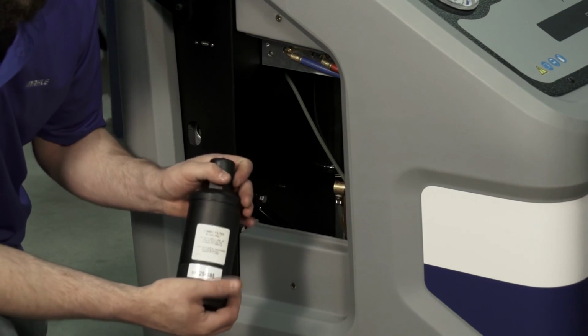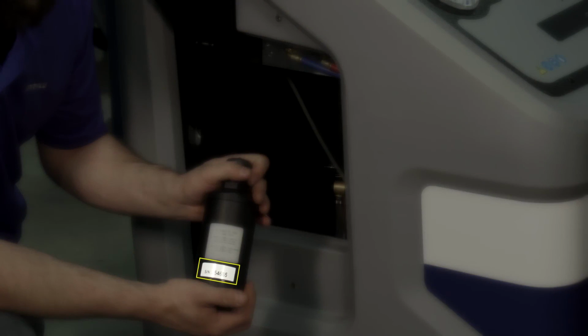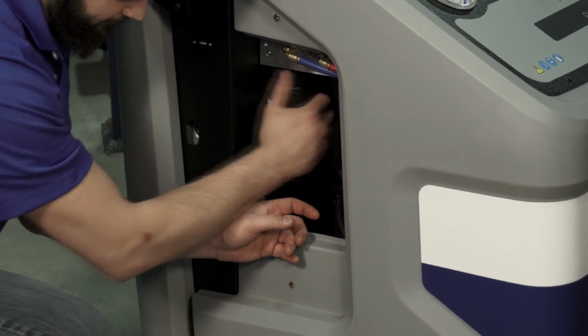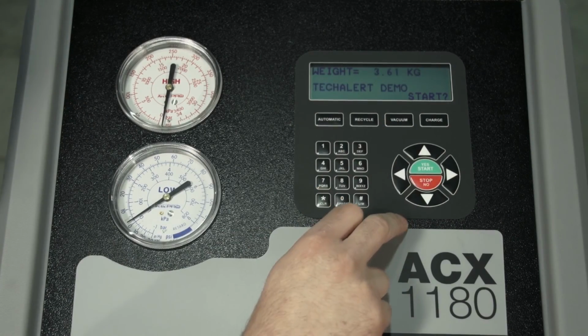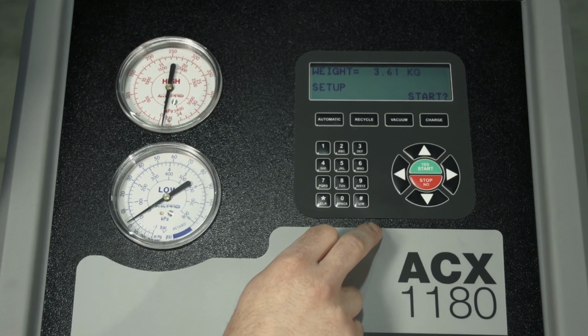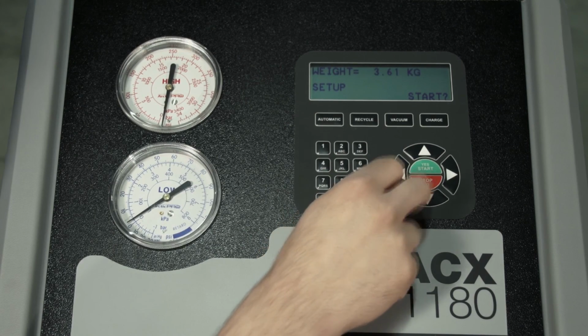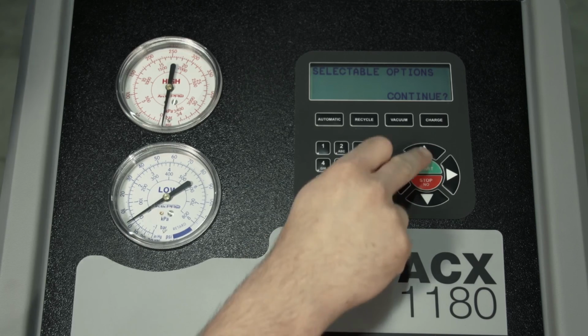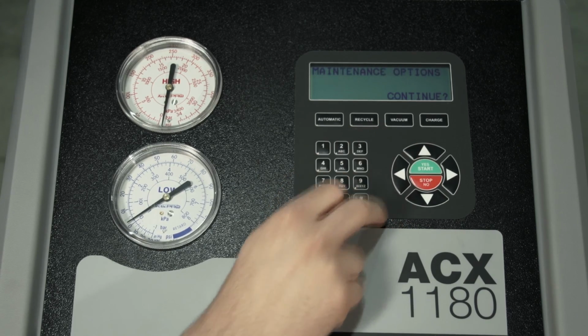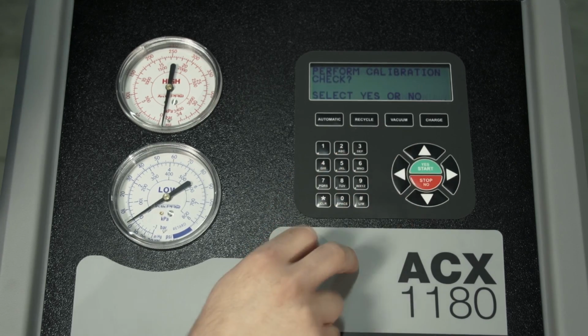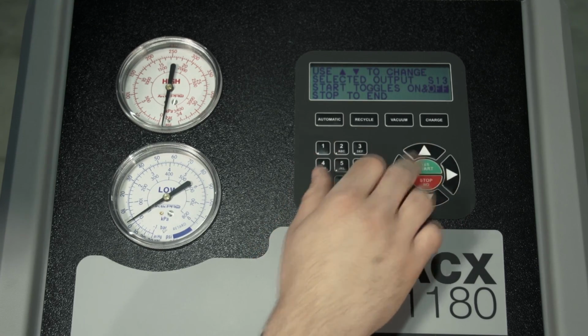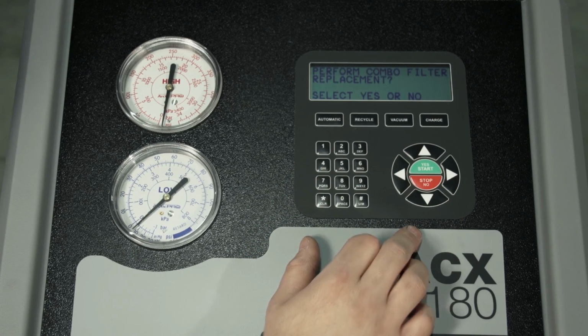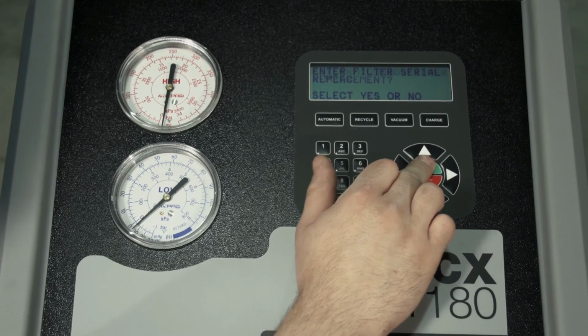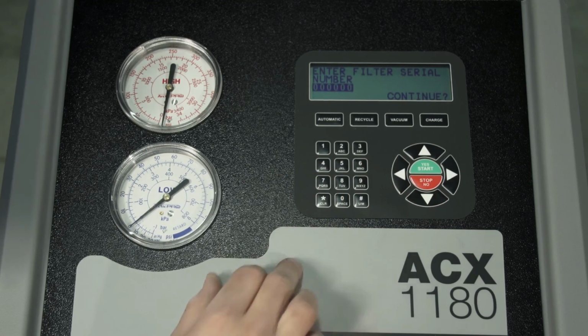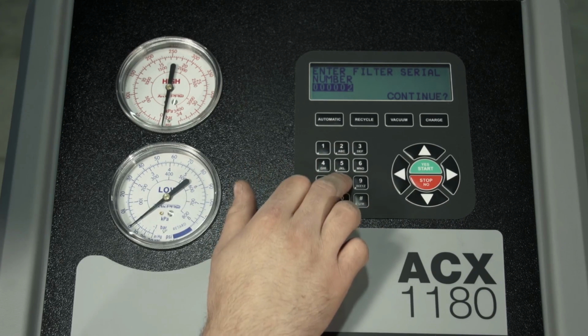Before installing the new filter, make a note of the PIN number on the side of the filter. Install the new filter and replace the service door. To reset the filter replacement interval, use the up or down arrow keys until the display reads Setup. Press Yes. Press the up arrow until the display reads Maintenance Options. Press the Yes button and continue to scroll through the options until the display reads Perform Combo Filter Replacement. Press Yes and use the numeric keypad to enter the PIN number that was located on the side of the filter.